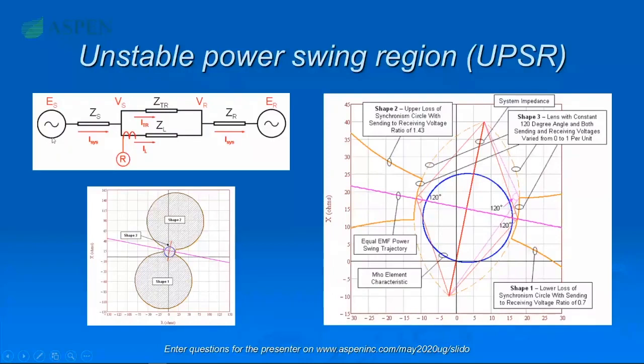PRC-26 defines these two circles forming a dumbbell, and on the right-hand side you see a magnification. There's a very detailed derivation of how those shapes work, but in short: your relay trip setting should not be encroaching outside of this dumbbell shape. If the apparent impedance appears inside the dumbbell, that represents — per PRC-26 — an unstable power swing, and you can and must trip. But if it's outside, your relay should not be tripping.